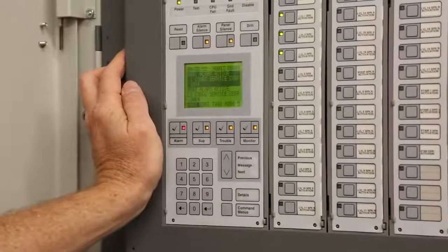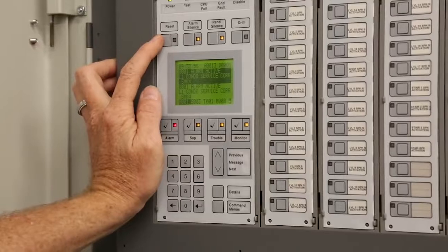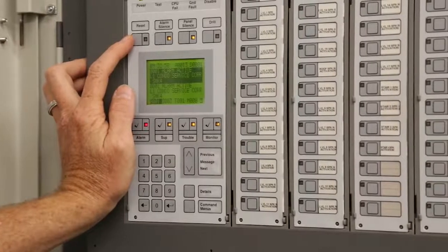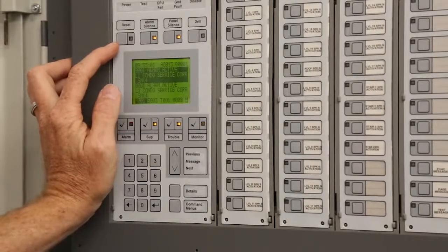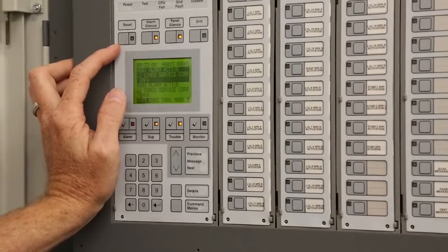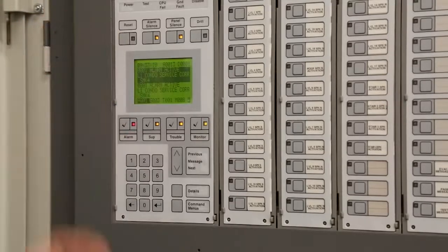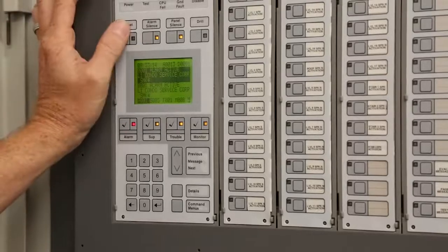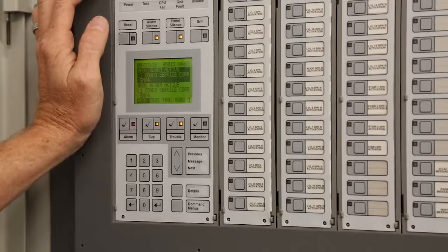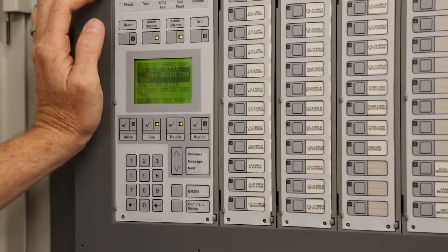You investigate it. There's no more smoke there. You can hit reset. Now, this thing, if that smoke detector still has smoke in it, it will not resound or refire if there's smoke in it, and it's still an alarm. Some systems you hit reset, all of a sudden it'll re-trigger and everything goes back in alarm. If that detector still has smoke and you hit reset, it'll just stay the way it is, okay? We'd have to bypass it or something. But what I'm getting at, it won't refire.